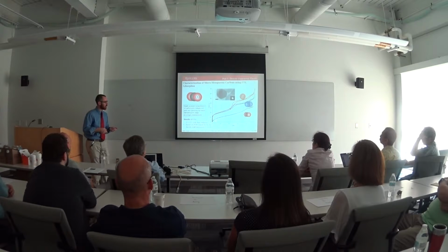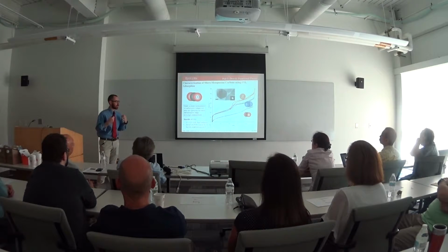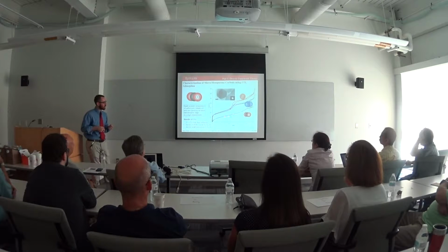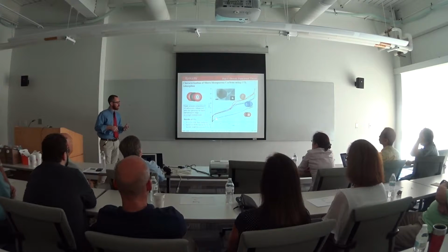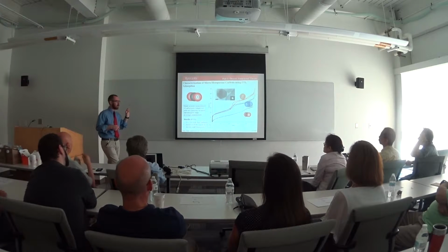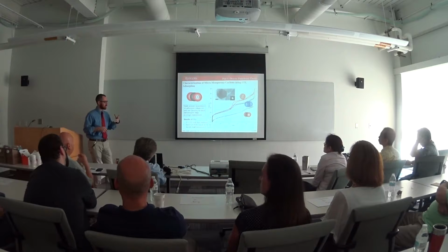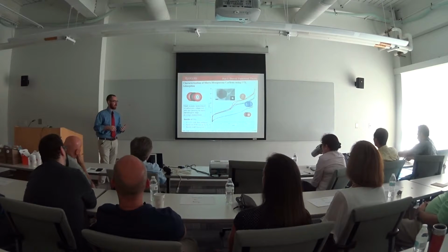However, we run into a problem in the very low relative pressure range in that we lose some of our experimental accuracy in the absence of very low pressure turbomolecular pumps. So what researchers have done in the past 20 or so years is started to look at using additional analysis gases such as carbon dioxide. And what they were doing up until very recently was just looking in the relative pressure range down here to look at the adsorption of CO2 in these really tiny micropores. Because it's done at a much higher temperature, carbon dioxide can penetrate into the smallest micropores of your material a lot faster and a lot more accurately than argon and nitrogen can.